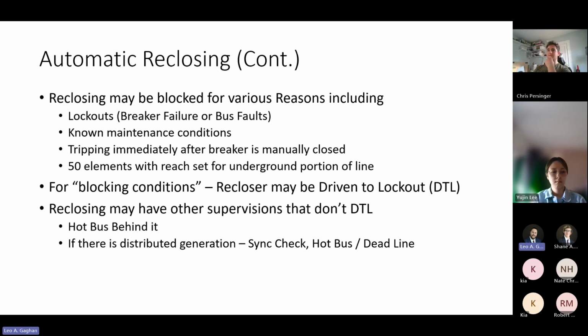We've got that breaker hold that we did in class the other day, right? Someone may have a lockout tagout, where we know that people are going to be working around energized equipment. Just turn it off to be safe. Another one: tripping immediately after a breaker is manually closed. That is usually indicative of something called switch on to fault. We won't get into that.